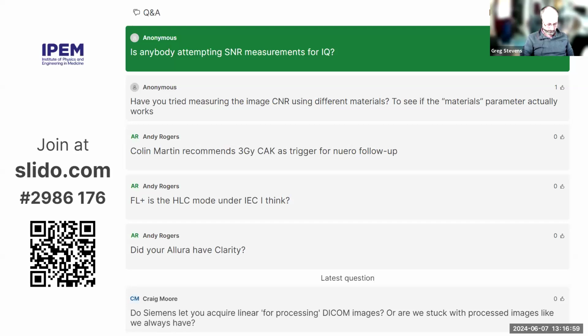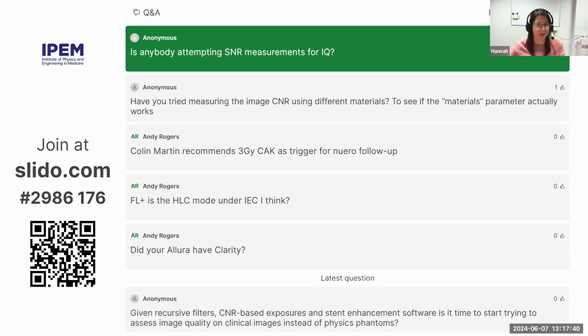I personally think that something along those lines is going to have to happen, because the reason we test fluoroscopy machines in the way that we do, measuring patient dose and eye face dose in the way that we do, is simply because the thing that's constant is the dose rate, or the air kerma rate, whatever you want to call it. Now we've got a CNR rate. We've got to either be able to measure CNR, or at least be able to infer it from somewhere. Yeah, it's fundamentally changing our thinking of what we're measuring, isn't it?